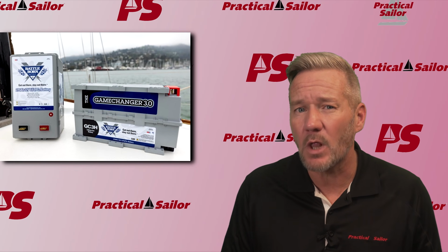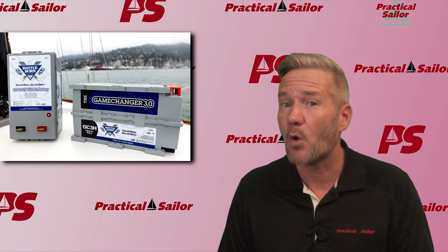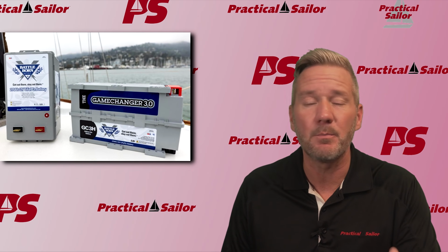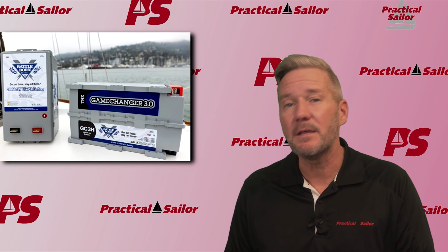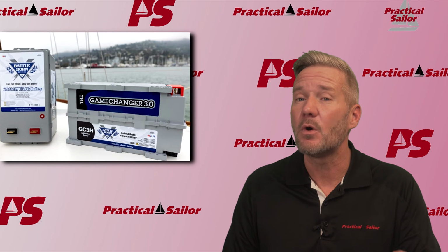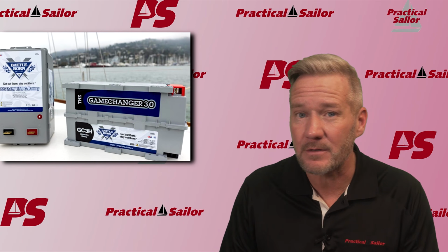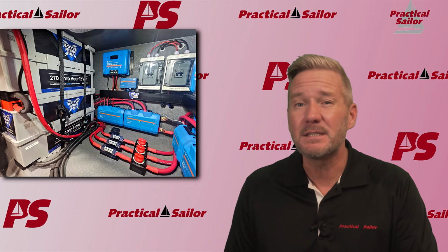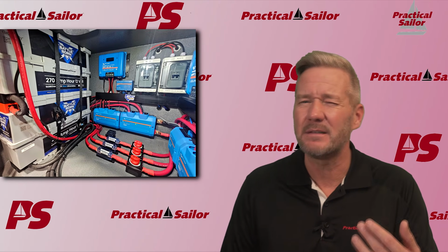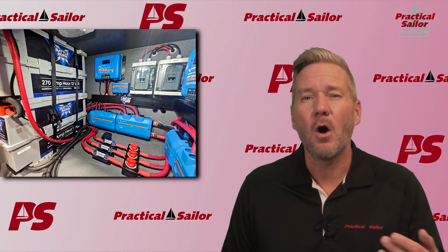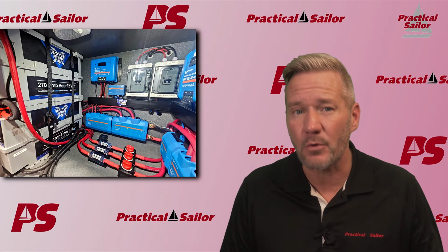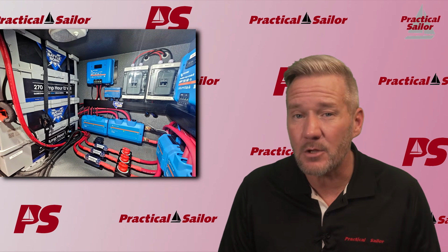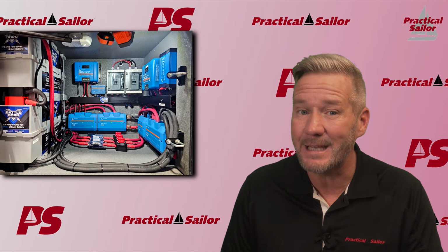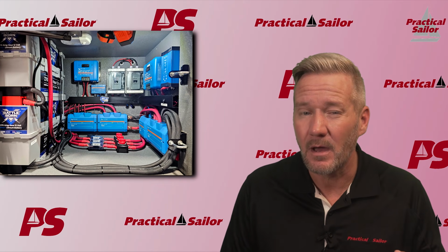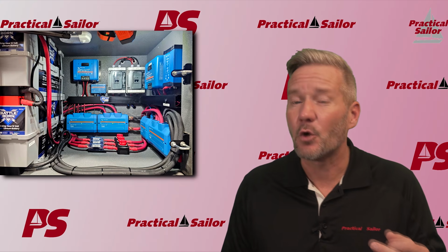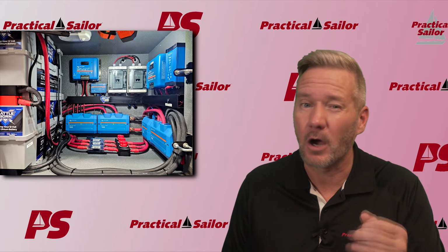If your lithium system relies on the BMS to intervene during normal operation, the system is already poorly designed. A good lithium installation is engineered so the BMS almost never activates. It shouldn't have to. It's there for faults and emergencies, not daily operational conditions. Overcurrent protection, charge control, system logic, and load management should prevent the battery from ever needing to pull that emergency brake. If the BMS is busy, your wiring diagram deserves a long, hard look.